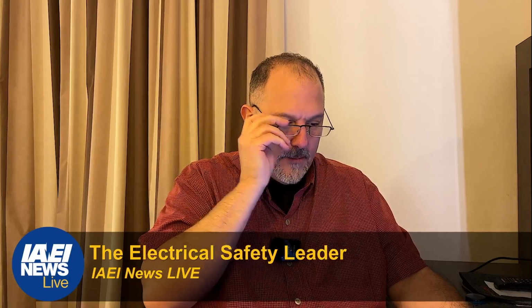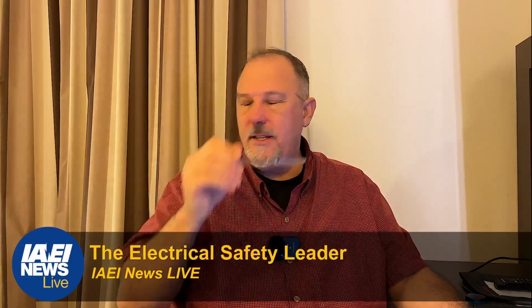Then they do a mechanical endurance test. This is 6 devices which were previously subjected to the above probe test. Oh my God, those poor devices. Gosh. A machine continuously inserts and withdraws an attachment plug having secured solid brass blades 5,000 repetitive times. So think about it. Some of these receptacles go through a heck of a lot, and this is a tamper-resistant receptacle.